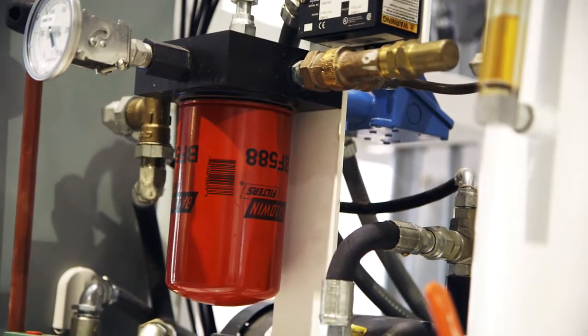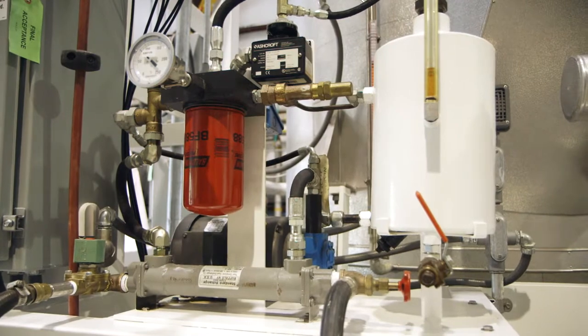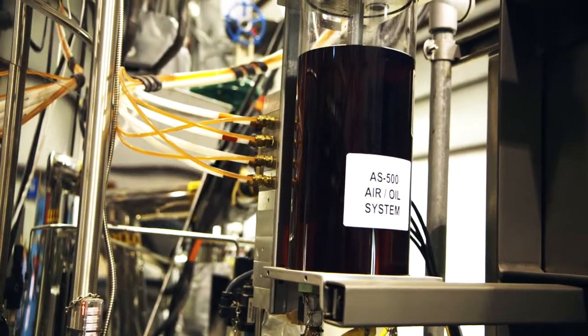One of the least desirable features of traditional vapor compression systems is the oil system associated with the compressor. These old oil systems use a pump to recirculate gallons of oil through a cooler, filter, and distribution block. They put a burden on the seals and eventually leak, and require an oil filter change and oil every six months. The new G2 technology uses air to cool the bearings, so we don't have to recirculate oil. We mist the bearings every few minutes with oil in a once-through system to lubricate them. With the new G2 oil system, we don't have oil seal leaks, we don't have to change out the oil filter and oil — we just refill the reservoir with about two quarts of oil a year.